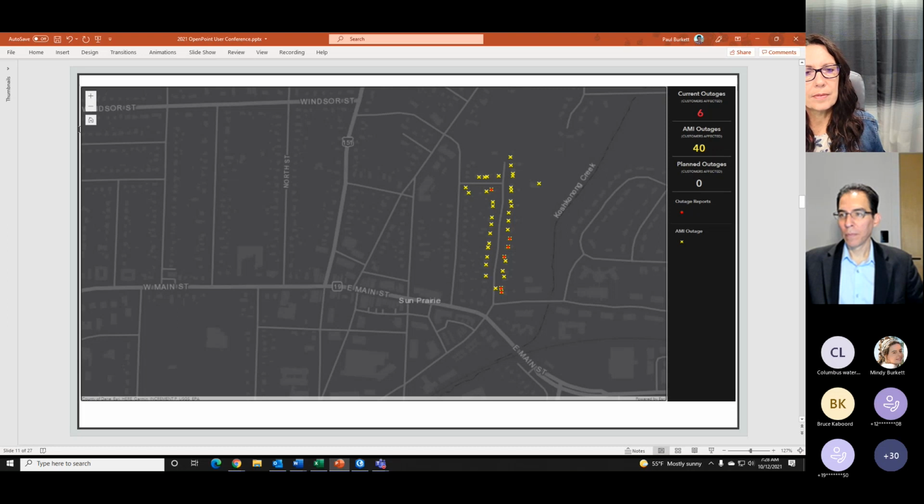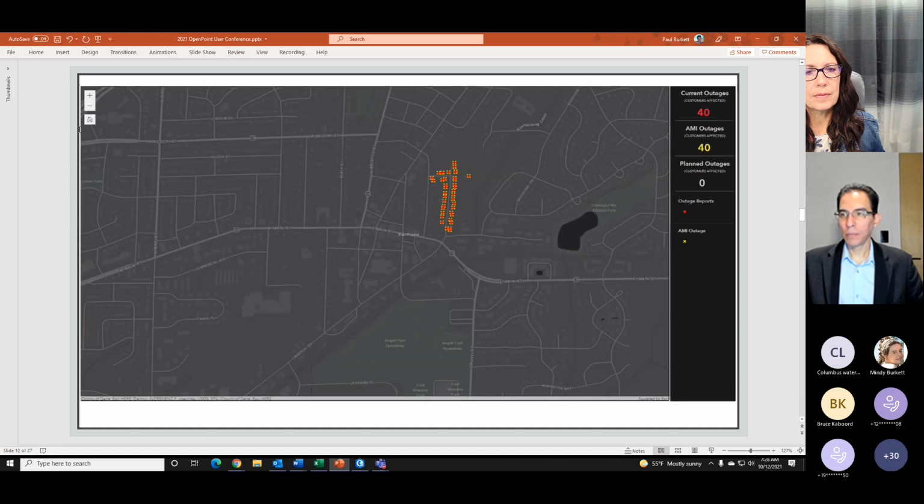And so once that happened, then I was able to select those AMI meters, and now I could add them to an actual outage report. So now everybody's added to this outage event, and that's the way of making sure that we're tracking this properly for use later on. And the one thing, when this happened, I think Carl both thought of it, and one of the line guys saw the benefit: they knew a squirrel had got a fuse on one of the transformers, but it didn't just blow that fuse at the transformer, it blew the fuse down the line too, so it actually took out everybody.